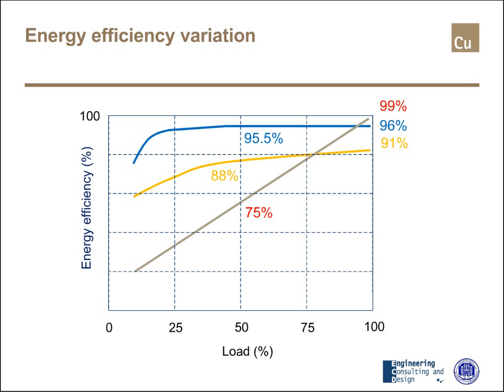Today, practically all manufacturers offer modular UPSs. This is very good from this point of view, because with a modular UPS I can activate modules as needed, and the efficiency-versus-load curve is much flatter than in traditional designs.